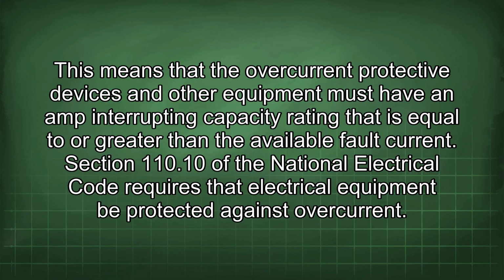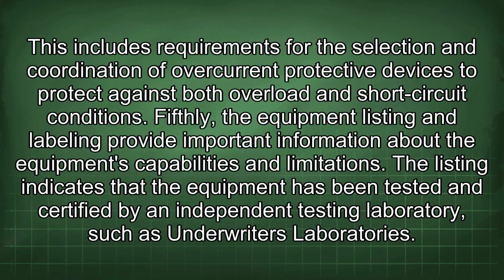Section 110.10 of the National Electrical Code requires that electrical equipment be protected against overcurrent. This includes requirements for the selection and coordination of overcurrent protective devices to protect against both overload and short-circuit conditions.